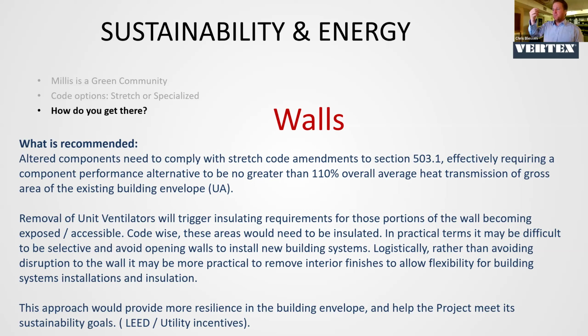If we talk about removing unit ventilators to go to a more broad-based mechanical ventilation system, with whatever heating and cooling system we decide to use, those unit ventilators will come out and we need to plug that hole with something, and that intervention is going to have to be code compliant.